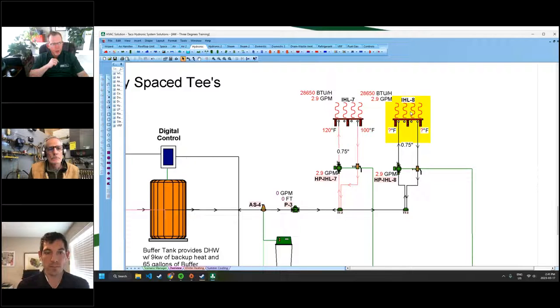So where we already have a bottleneck of how high we can lift that water temperature, we don't want to be doing closely spaced tees, because you'll get a temperature cascade across those tees. Now, it's not going to be a matter of the first one was fed 120 and the next one gets 90. The first one will get 120 and we don't know what the second one's going to get. None of us are doing that math. But the reality is we have firsthand experience where people have done this and done six manifolds with closely spaced tees on a heat pump, and that last zone on the coldest day may not get warm enough. So you could get phone calls of, why is my master bedroom cold? And the only thing that happened was closely spaced tees on that.